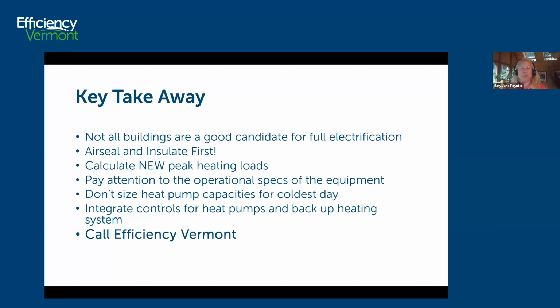Don't size for the absolute coldest day. Don't size for -20, -15, and even -11 might be too cold to try to size for. So look at what 0 would look like. Integrating controls for heat pumps and whatever the existing heating system are in the building can be complicated, and it's something that you really need to give thought to. Work with your engineer or mechanical contractor, work with the manufacturer of the heat pump to find out what thermostats can integrate with your old system.